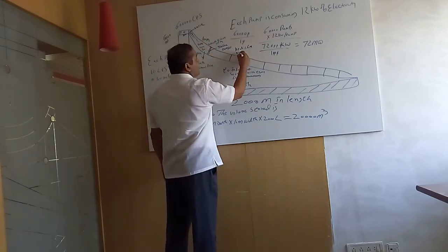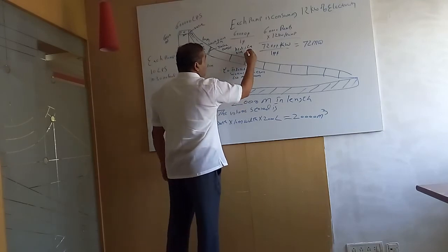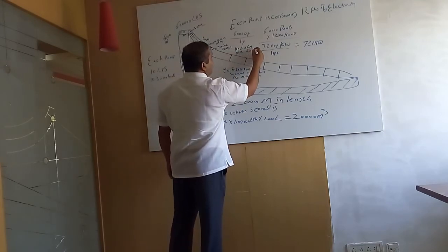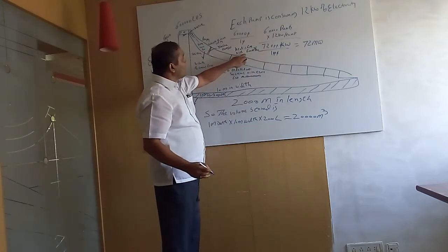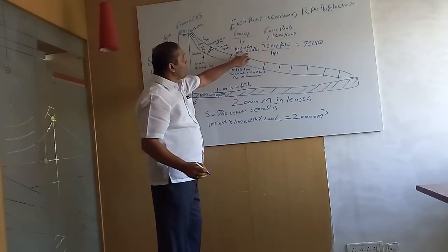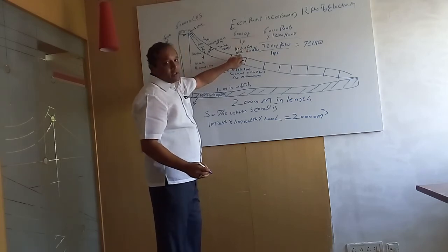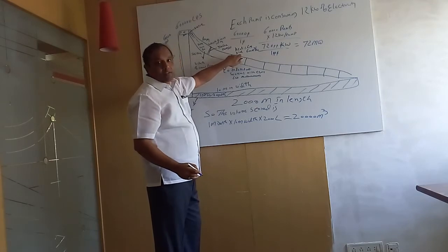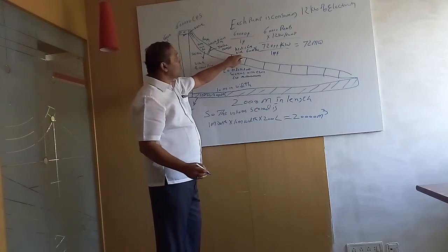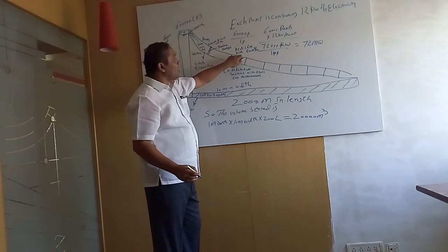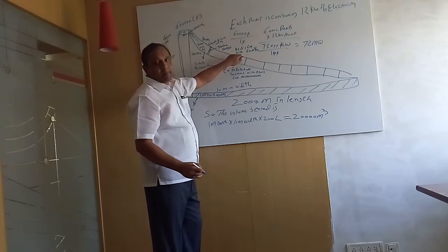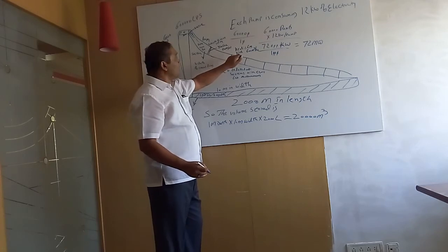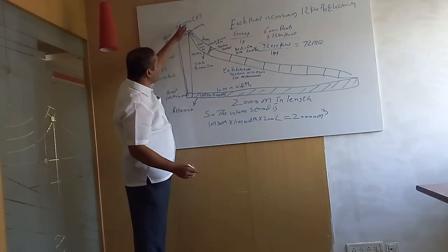The discharge is 600 meter cube per second. So the discharge is 600 meter cube, the head is 6 meters. In this way we are going to get 20 megawatts, because head into flow or discharge into gravity into efficiency is the power generation for that particular sector.